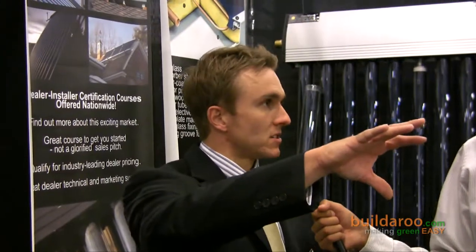You also have a water tank right here on the side. Can you talk a little bit about its features? We utilize these SunMax solar water tanks in situations where people want to store some hot water for later use. Obviously the sun isn't out 24 hours a day, so during those hours when the sun isn't out, you can use what you've collected all day with the evacuated tubes, store it in that tank, and pull from it on cloudy or rainy days or at night. Those are some of the features that make a water tank advantageous compared to having a tankless heater.